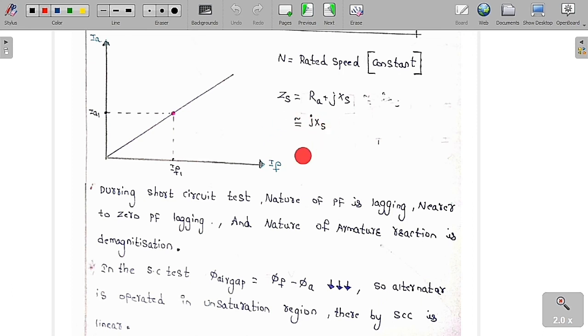So it is nearly equal to zero power factor lagging, and the nature of armature reaction is demagnetization. I've already told this important point: in a synchronous generator or alternator, whenever there is a pure lagging load, the IA lags EF by 90 degrees. So phi A and phi F are quite opposite of each other, and therefore a demagnetization effect occurs.